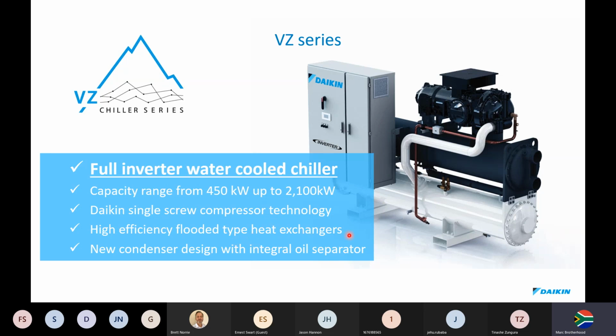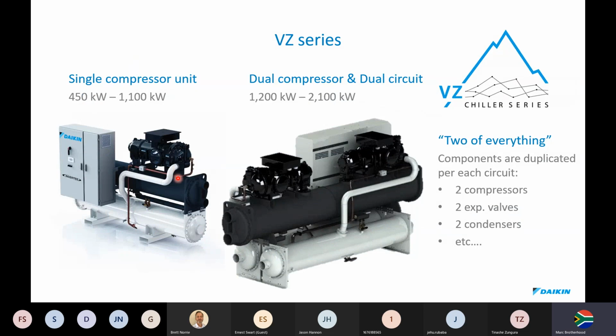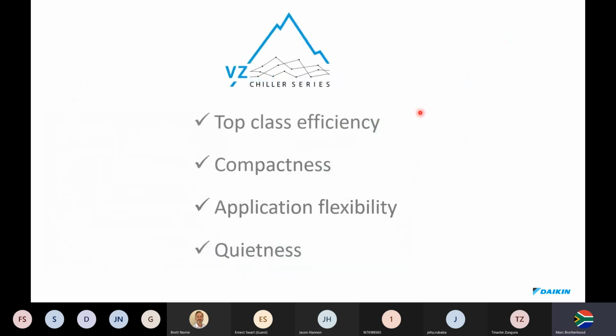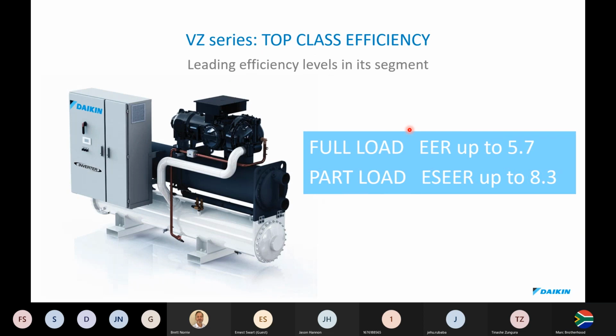We offer high efficiency flooded heat exchangers, and we have a new condenser design with a built-in oil separator, which I'll show you. We go up to 1.1 megawatts in the single compressor unit, and then we offer a dual circuit, double compressor unit up to 2.1 megawatts. So everything is doubled on this chiller. We offer top class efficiency, compactness, application flexibility, as well as quietness. This chiller is also very efficient, up to 5.7 at full load on energy efficiency, and seasonal energy efficiency up to 8.3.